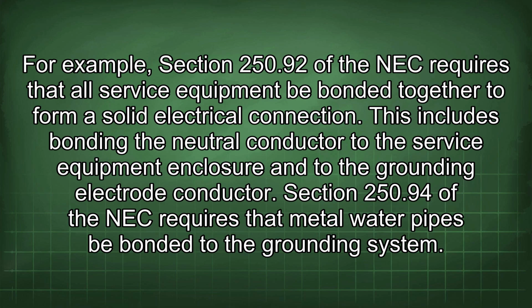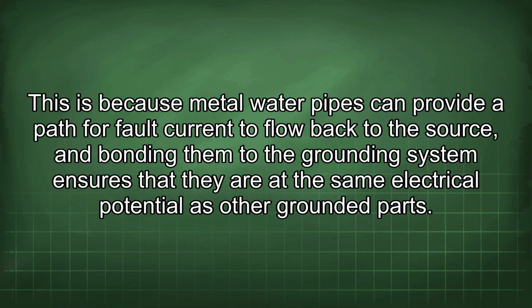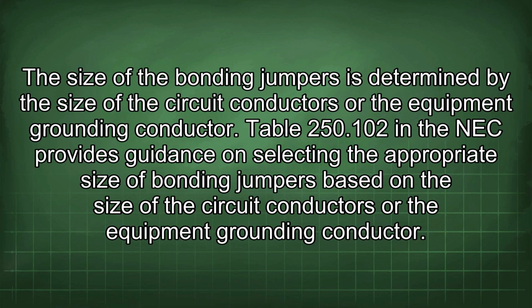Section 250.94 of the NEC requires that metal water pipes be bonded to the grounding system. This is because metal water pipes can provide a path for fault current to flow back to the source, and bonding them to the grounding system ensures that they are at the same electrical potential as other grounded parts. The size of the bonding jumpers is determined by the size of the circuit conductors or the equipment grounding conductor.